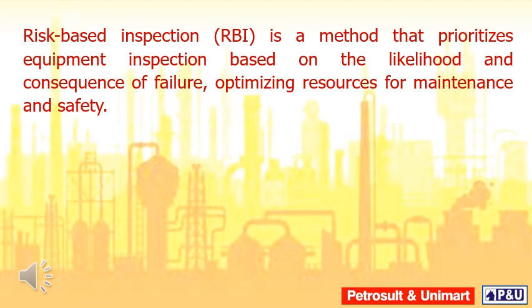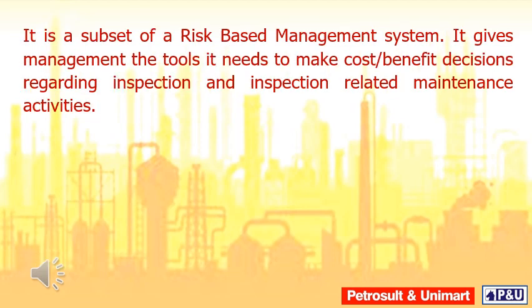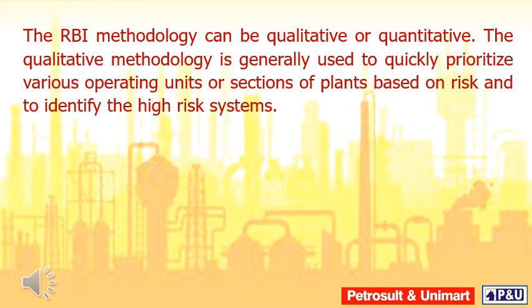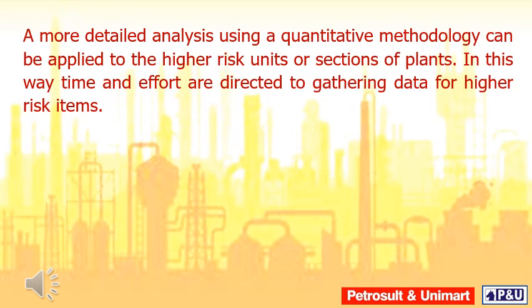Risk-based inspection (RBI) is a method that prioritizes equipment inspection based on the likelihood and consequence of failure, optimizing resources for maintenance and safety. It is a subset of a risk-based management system and gives management the tools needed to make cost-benefit decisions regarding inspection and inspection-related maintenance activities. The RBI methodology can be qualitative or quantitative; the qualitative methodology is generally used to quickly prioritize various operating units or sections of plants based on risk and to identify the high-risk systems.